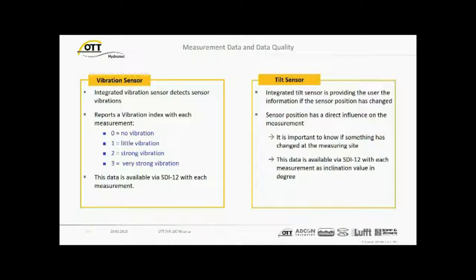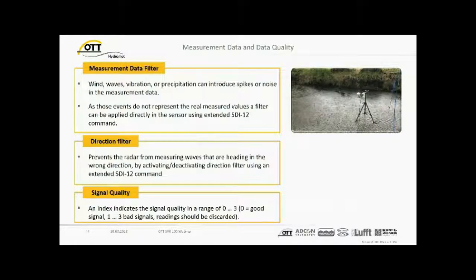A tilt sensor is also integrated to provide the user information about the sensor position, if the position has changed, because the tilt angle is part of the computation of the surface velocity by cosine function. The sensor position has a direct influence on the measurement, so it's very important to know if something has changed on site due to vandalism, due to very strong wind gradients, whatever happens in the field. This data is also available via SDI-12 with each measurement as an inclination value in degrees.